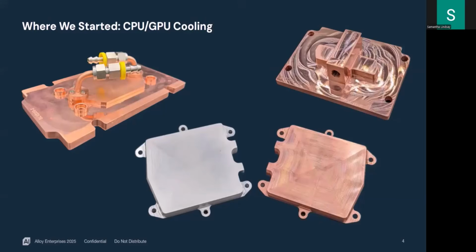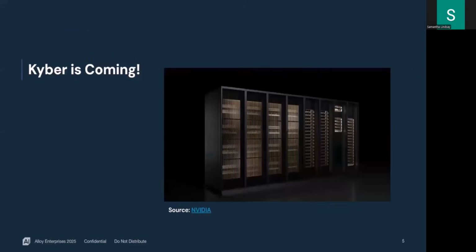Well, first off, Kyber is coming. NVIDIA announced the Kyber rack, I believe, just about a year ago now. This will be the rack system that supports the Vera Rubin CPU-GPU pair, the next generation system. They're projecting this is going to have 600 kilowatts of heat in a single rack. 600 kilowatts, that is massive. It's well beyond where we are today, where leading edge racks deploying today are pushing 120 kilowatts.